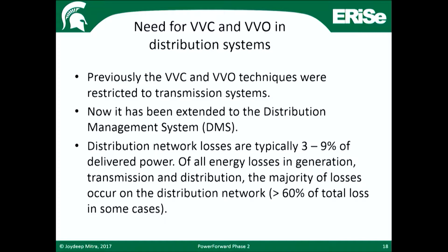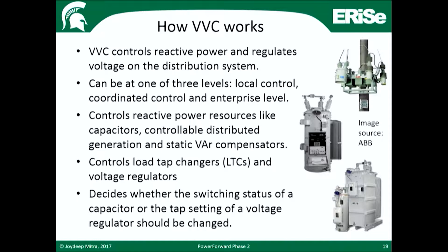In the past, this used to be restricted to transmission systems, but of late it has grown into the distribution arena as well. We try to reduce losses primarily through Volt-VAR control, which is achieved by controlling three kinds of devices in the system: capacitors and other devices that inject reactive power into the system, and load tap changers and voltage regulators that adjust the voltage in different parts of the system.